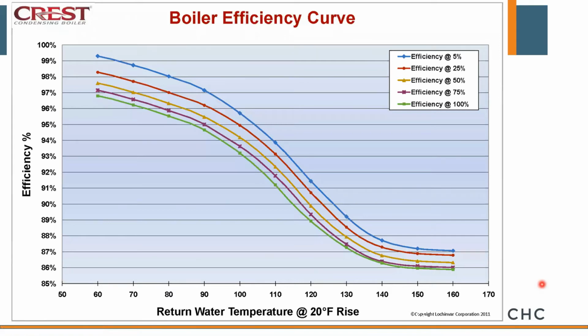So all manufacturers have efficiency curves. I'm showing you a Lochinvar Crest, but again, all manufacturers offer their curves, and you'll notice they're all very similar. So what you're going to see here is a manufacturing statement that says, hey, this boiler is up to 99% efficient. The question is, how do you get a product to be 99% efficient? Because that's a pretty good number. Well, if you look at this point, in order to get to be 99% efficient, we have to be at low fire, okay, or minimum fire in this case. And we also have to have 60 return water coming back to our boiler. So very cold water and minimum firing rate.